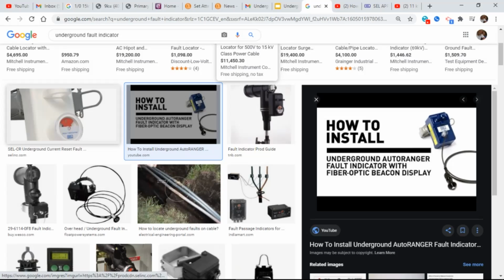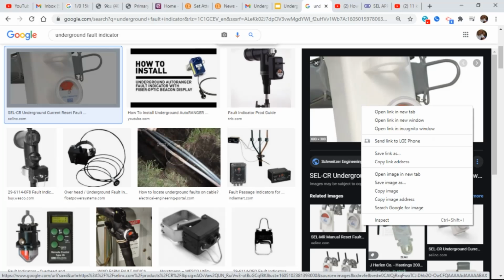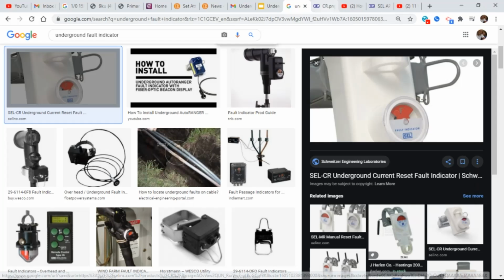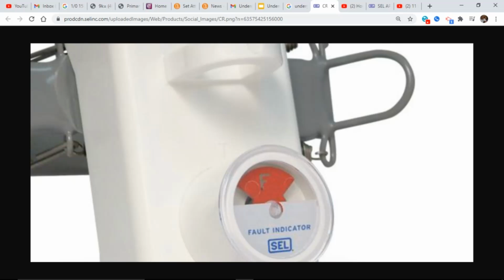So let me go over here. Here's one, and there are different types. We did move to the fiber optic type. Eventually, but this is one that straps around the primary conductor but has no remote indicator. You have to open the door and actually look at the indicator, and this one is showing fault. If it was clear, this flag would turn around, you'd see a white flag, and I don't know why they put this in there with an N in it. I don't know what they put the N in it for, but showing white, your cable is clear. You've got good cable.